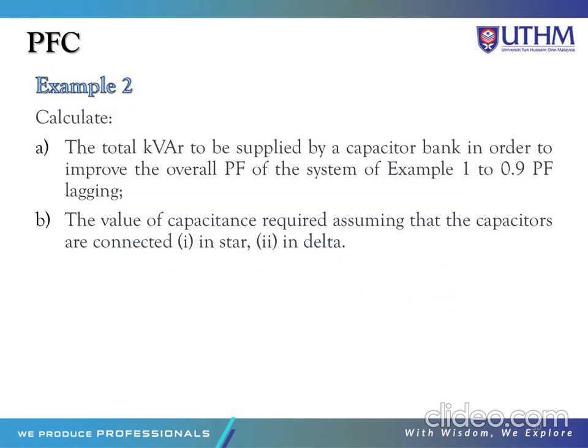Next we go to example 2, for power factor correction. Calculate A, the total kVAR to be supplied by a capacitor bank in order to improve the overall power factor of the system of example 1 to 0.9 power factor lagging. B, the value of capacitor required, assuming that the capacitors are connected first in star connection and second in delta connection.